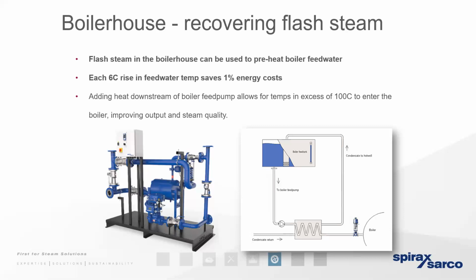So for smaller volumes, we can use that flash vessel that we've spoken about on the previous slide. But for larger volumes of flash, we can use what we refer to as a flash recovery energy management skid. That really uses both the flash steam and the condensate in different phases. We can pass it across a very simple heat exchanger to add energy to another process. The key here is recognizing a process where a significant amount of flash steam is likely to be produced.